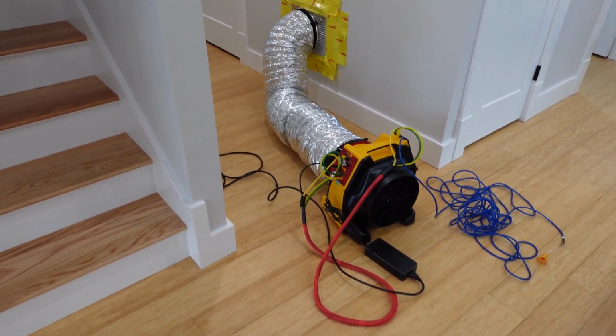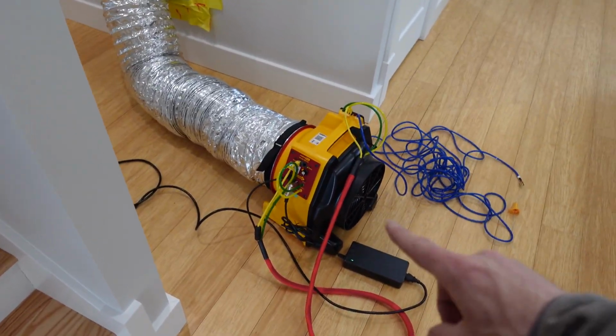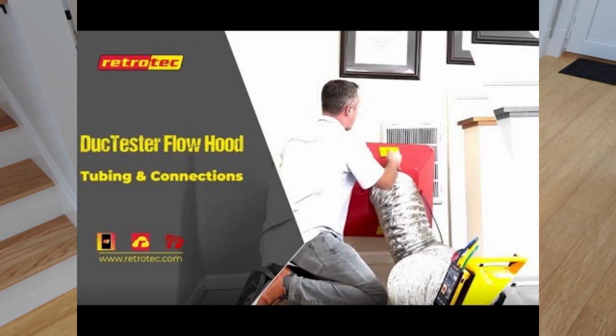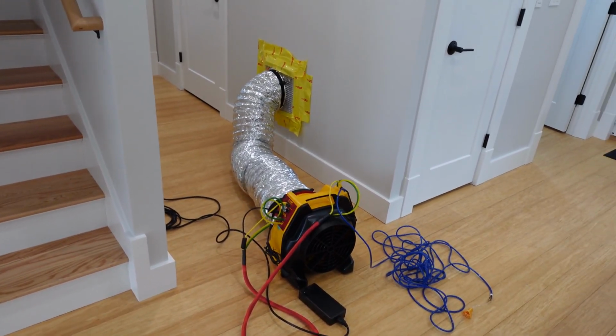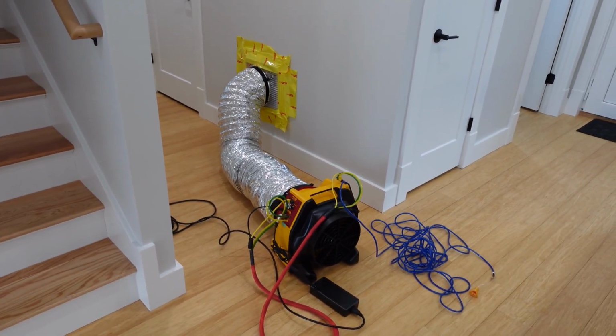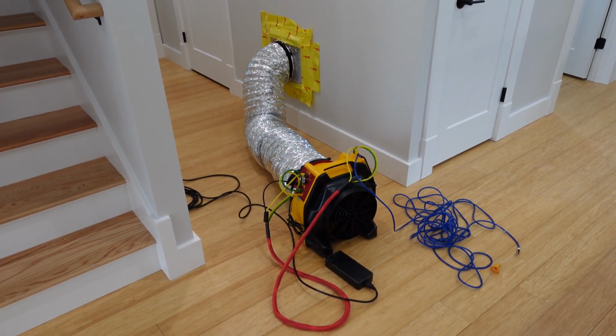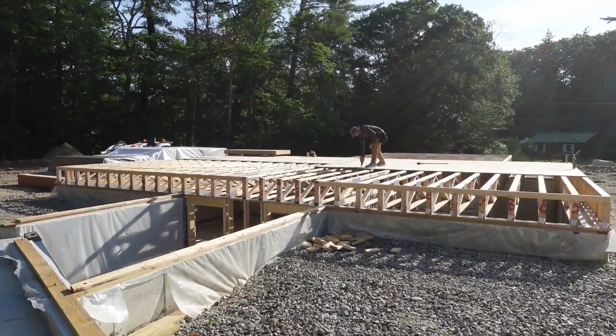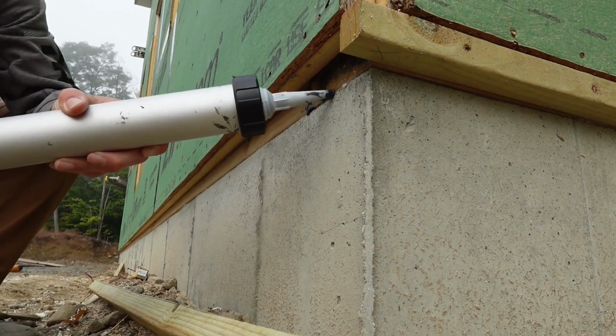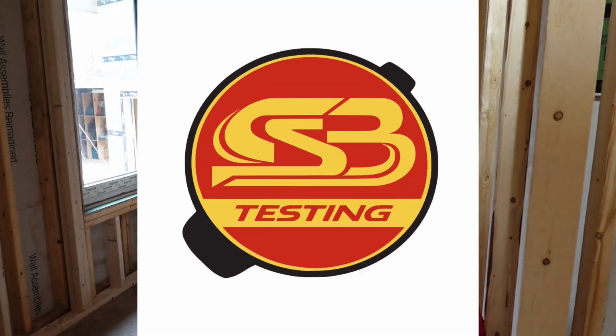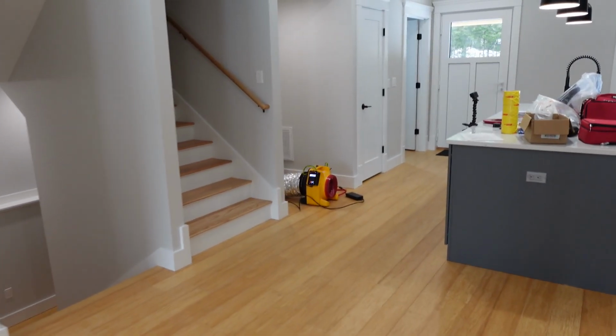The second test is going to be pressure balancing, using this as a flow hood and testing the system airflow. Now the first one is going to tell you how much is leaking, obviously. The second one is going to confirm how much airflow is actually moving into the conditioned space. To do those tests, we're going to use a Retrotec duct tester fan.